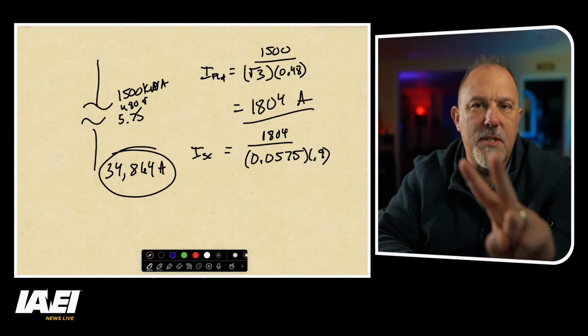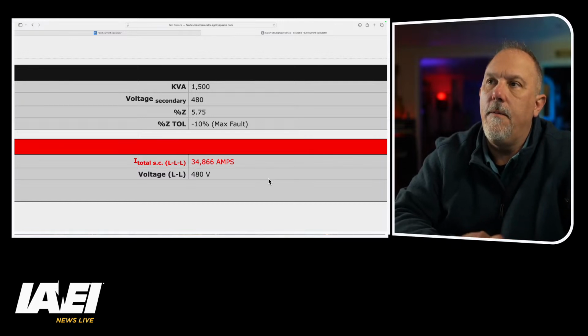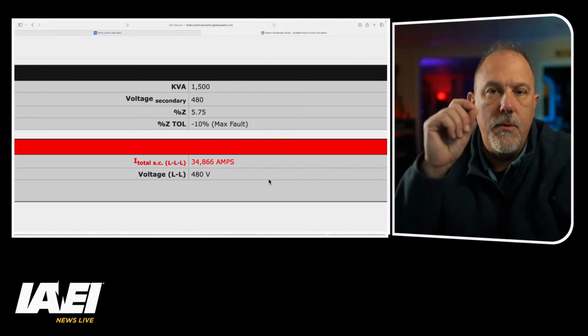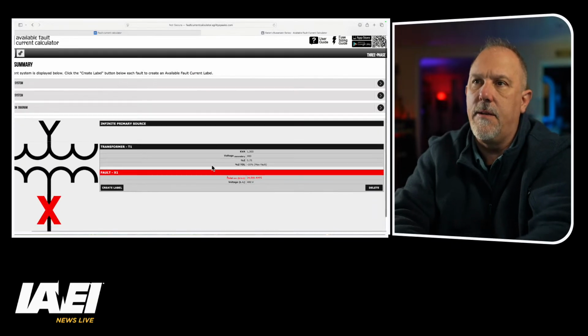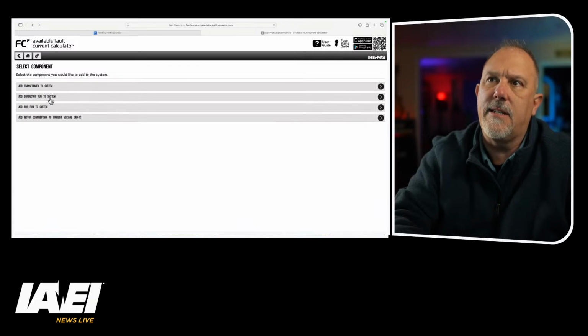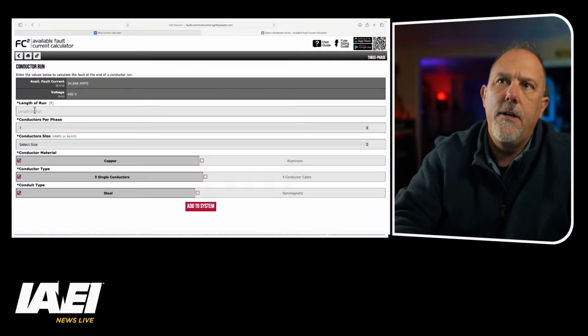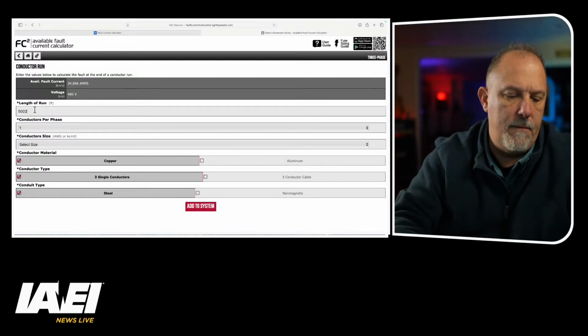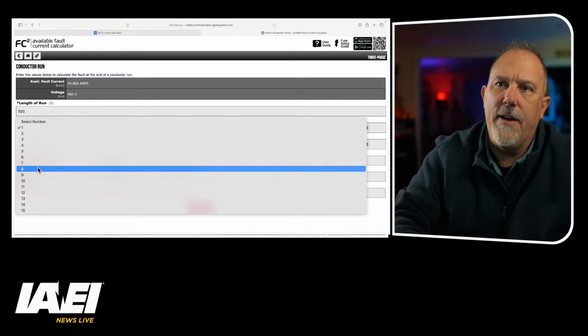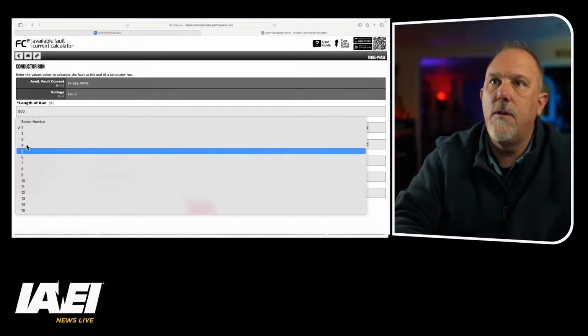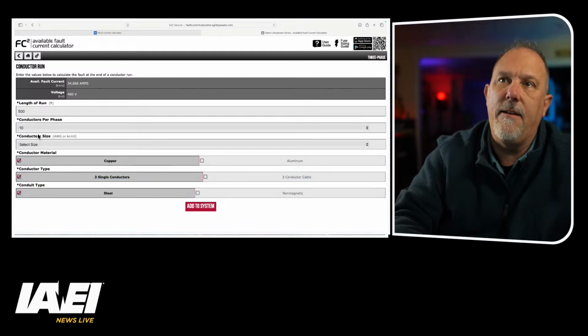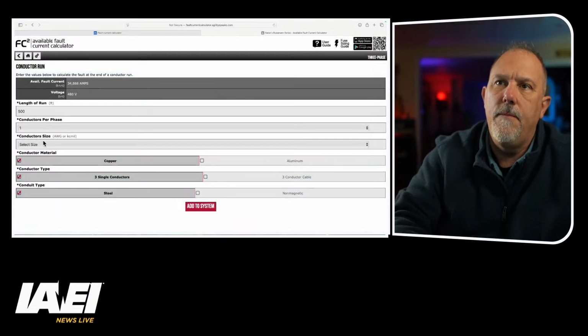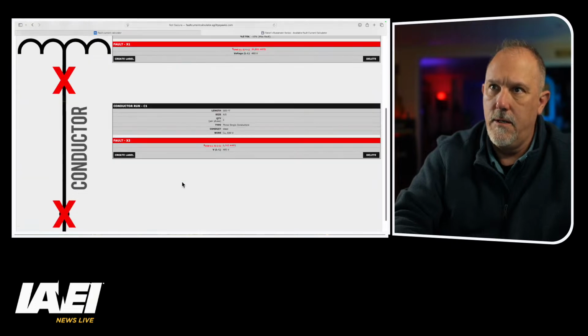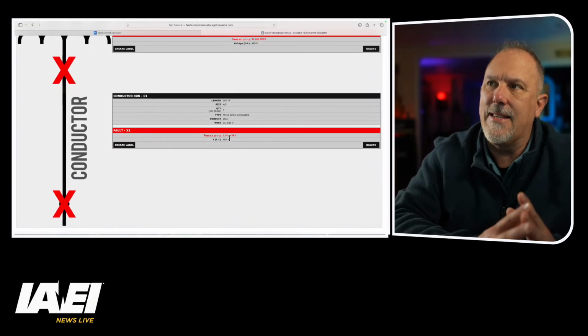34,864. I'm 2 amps off between those two. So this app helps you make life a little simpler. You could add to the system on a secondary. You can add a conductor run. You could add 500 foot of... how many in parallel? We'll say 10 in parallel. No, we'll say 1. Select the size, 4-aught. I'm just going to add to the system. There's your conductor, and now you know you're at 6,743.